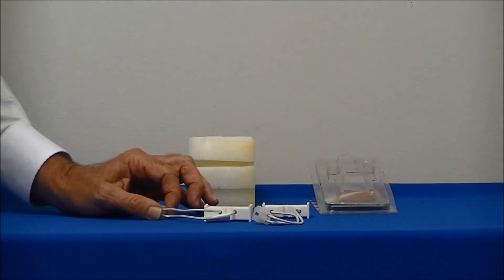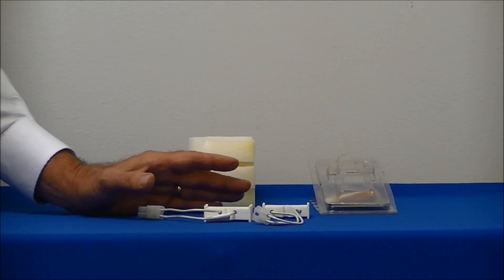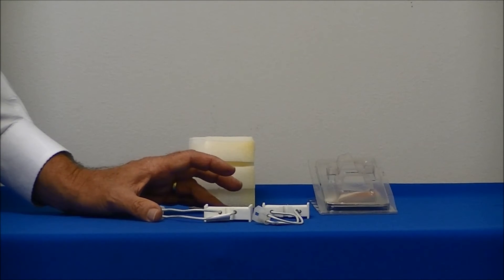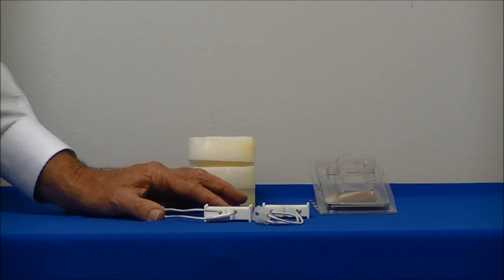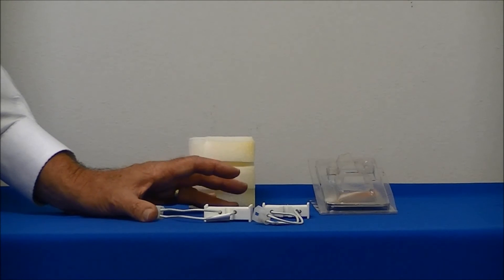The igniters are rated in voltage. Use the appropriate voltage as is required in the furnace. If the furnace requires a 120 volt igniter, do not put an 80 volt igniter in its place. If it calls for an 80 volt igniter, do not put a 120 volt igniter in its place.